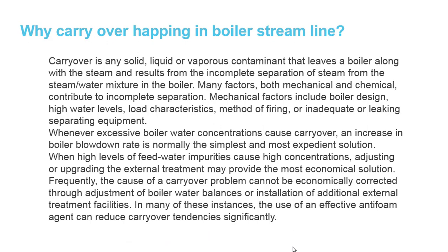Why is carryover happening in the boiler steam line? Carryover is any solid, liquid or vapor contaminant that leaves a boiler along with the steam and results from the incomplete separation of the steam from the steam and water mixture in the boiler. Many factors, both mechanical and chemical, contribute to incomplete separation. Mechanical factors include boiler design, high water levels, load characteristics, method of firing, and inadequate or leaking separating equipment.